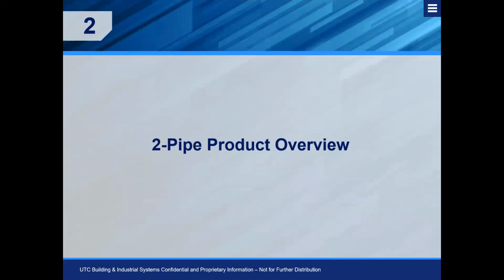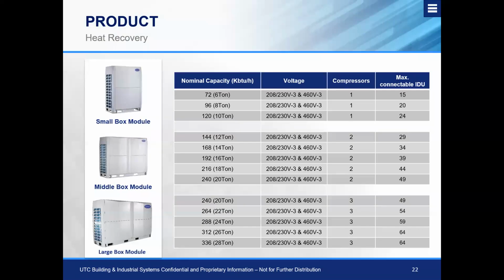Okay, so let's switch gears and take a look at the 2-pipe product. So with the heat recovery 2-pipe product, we have our small box, medium box, and large, just like we talked about before in the generalized overview. Now you can see on our 6, 8, and 10-ton modules, we have 1 compressor per outdoor unit, and depending on what tonnage we're working with will dictate the maximum connectable number of indoor units.